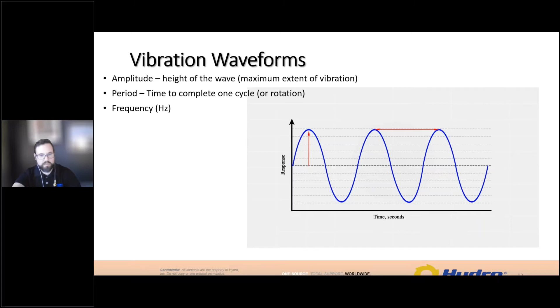The third characteristic of vibration that you need to know about is phase. Phase is sometimes the trickiest one to conceptualize, because any single point on a machine doesn't have phase. Phase is only in relation to different points on a machine—from end to end of a bearing housing, from the motor to the pump, from different places.